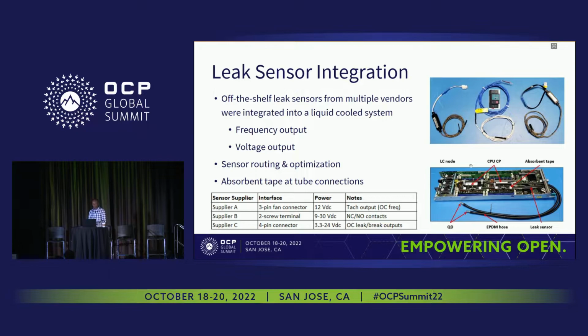And the other thing, normally, you might have seen some of these rope-based leak sensor implementations in pipeline applications. Normally, they put them at the lowest point in the system. Maybe if they put it under a rack or any kind of spill containment, they put those ropes. And if there is a leak, it's going to either signal an alarm or trigger or take some action as a mitigation point. So this is primarily based on gravity, right? So what we try to do here is to optimize and make these leak sensors more of an active type of detection rather than passive.